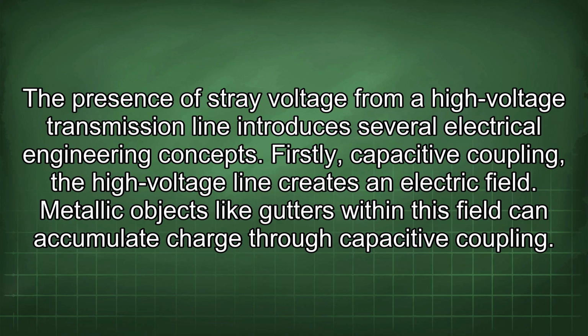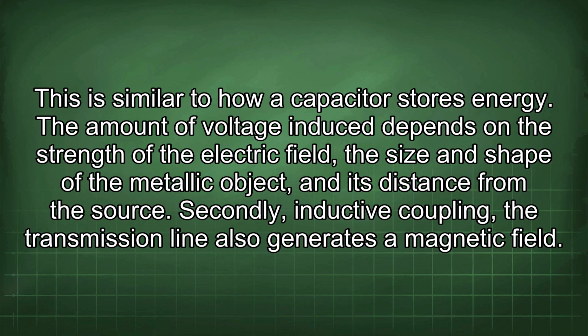Firstly, capacitive coupling. The high voltage line creates an electric field. Metallic objects like gutters within this field can accumulate charge through capacitive coupling. This is similar to how a capacitor stores energy. The amount of voltage induced depends on the strength of the electric field, the size and shape of the metallic object, and its distance from the source.